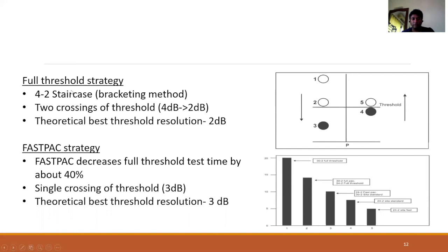The full threshold does a 4-2 bracketing technique with two crossings over the threshold. If the initial stimulus is seen by the patient, the stimulus intensity is reduced in steps of 4 decibels when it crosses the threshold once, then increased in steps of 2 decibels when it crosses again. The best threshold resolution is about 2 decibels. The FASTPAC strategy uses one crossing-over where the intensity is reduced in steps of 3 decibels, giving a best theoretical resolution of 3 decibels.